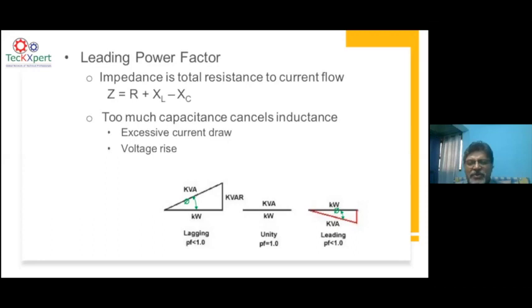This is an area where, when it comes to leading power factor, you have to use the right type of technology. There are solutions like what we call smart hybrid filters. A hybrid filter will have capacitors as well as an active harmonic filter together in one network. The capacitor bank and active harmonic filter are synchronized in such a way that the active harmonic filter will take a decision when to switch on a capacitor and when not to.